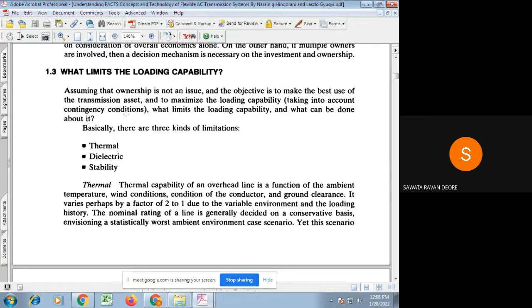According to that resistance, whatever maximum current we can allow to pass through that conductor, whatever copper loss, that is I squared R loss, takes place will heat the conductor, because that copper loss is converted into heat. That heat must be thermally sustained by the conductor, meaning the conductor should not break. On the basis of this, the current rating of that conductor has been decided.